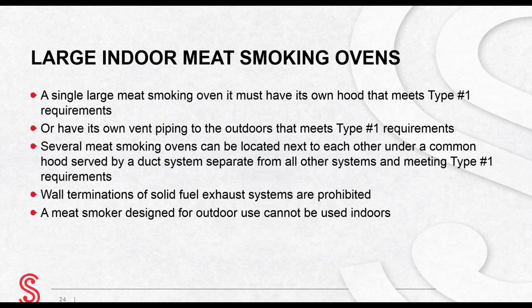A single large meat smoking oven must have its own hood that is served by a ductwork system separate from all other exhaust systems that meets NFPA 96 Type 1 requirements, or have its own vent piping to the outdoors that meets NFPA 96 Type 1 requirements. Several meat smoking ovens can be located next to each other under a common hood with solid fuel cooking equipment that is served by a duct system separate from all other exhaust systems that meets NFPA 96 Type 1 requirements. Other types of cooking equipment cannot be under this hood, only meat smoking ovens.